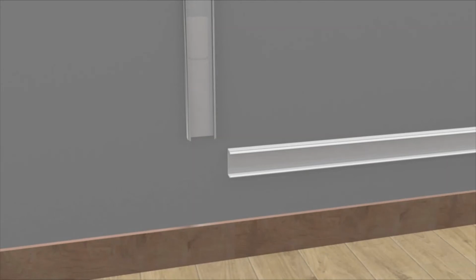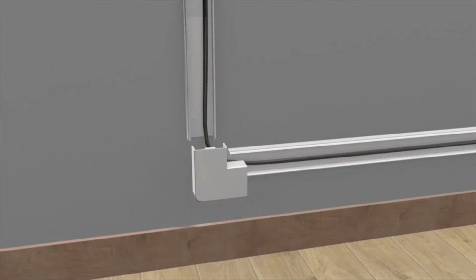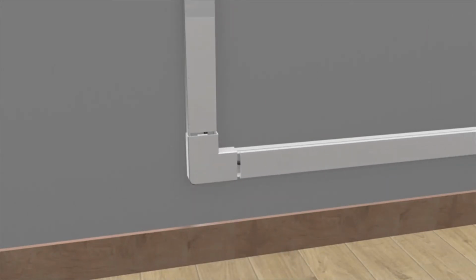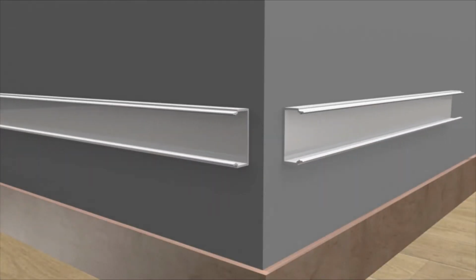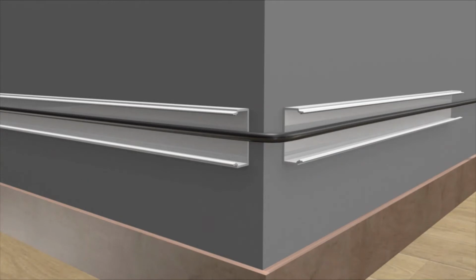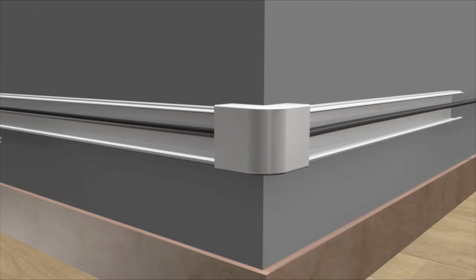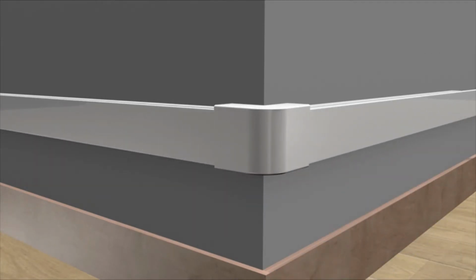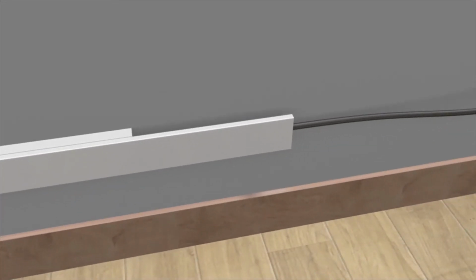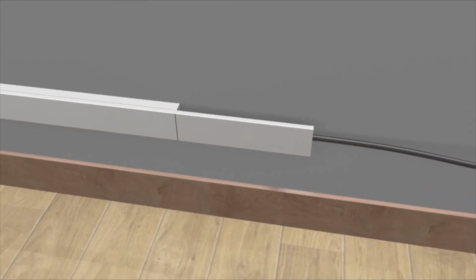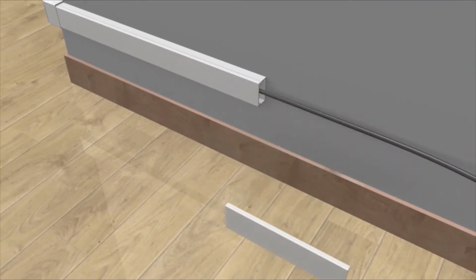Install the raceways as shown if you intend to use the 90-degree connector. Click the outside elbow connector to the raceway and slide the covers in place. You may have excess cover that needs to be cut to size. If this happens, simply mark with a pencil and use a hacksaw to cut the excess.